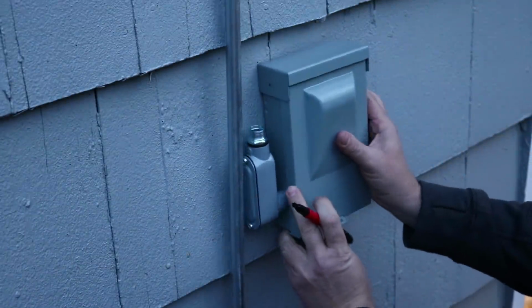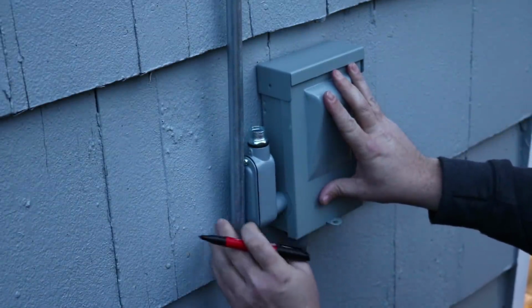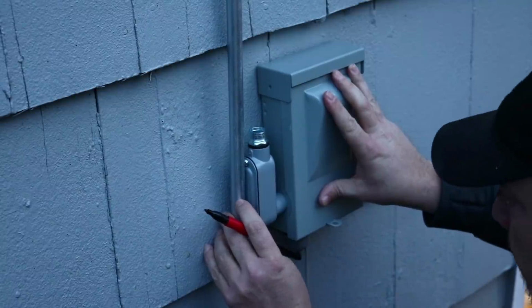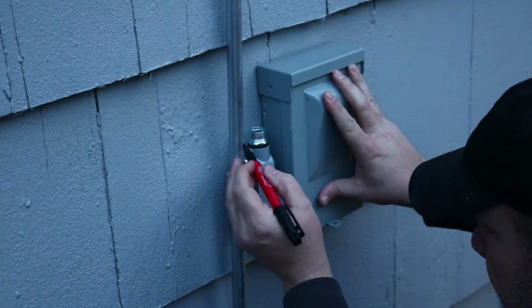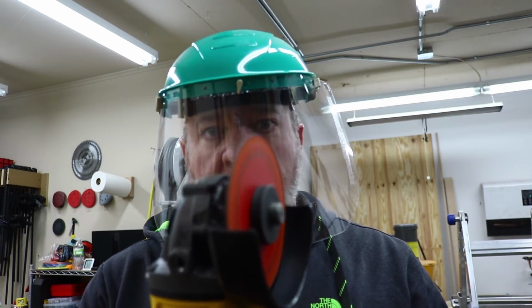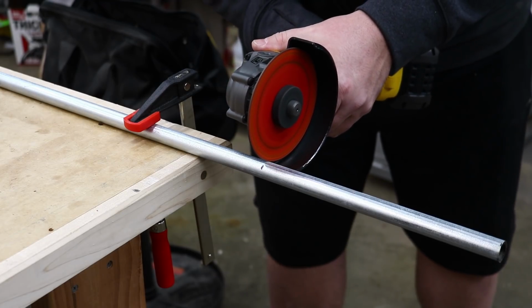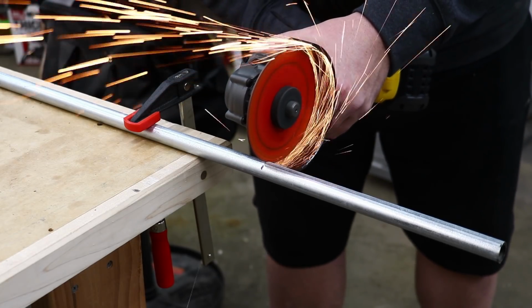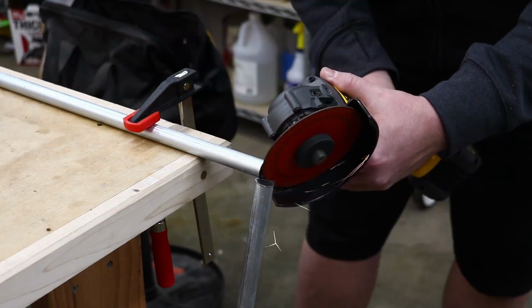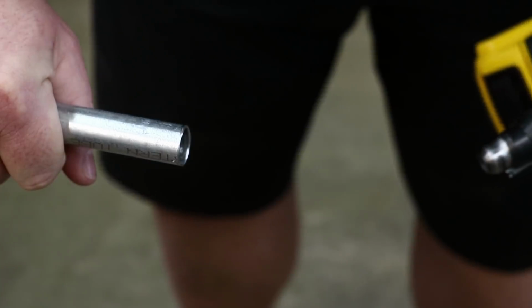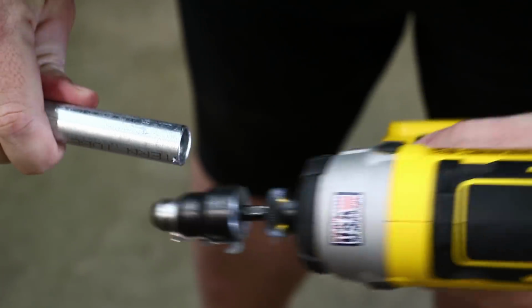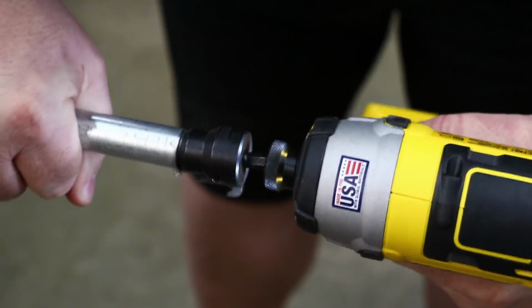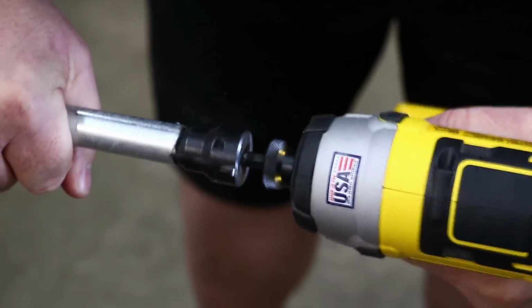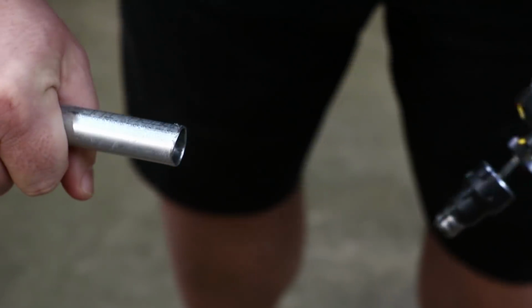With the disconnect box assembled, I could take it outside, put it where I wanted it on the wall, and mark the conduit so I could cut it to length. Safety first, kids. I then used the cutoff wheel on my grinder to cut the EMT to length, and then followed up with a conduit reamer to remove all of the burrs. Using one of these reamers is a necessity so you don't chew up your wire while feeding it through the conduit, and you don't mangle your hands while you're handling the material.